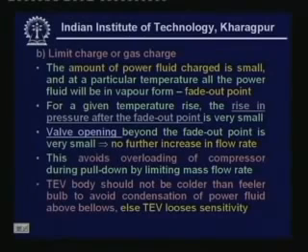Okay, whatever be the temperature, right? That means the flow rate reaches a particular value and it will not increase beyond that point. That means you are restraining the power input or power requirement of the compressor. Thereby you can avoid the overload of the motor. Okay.